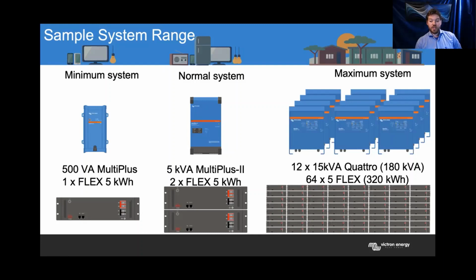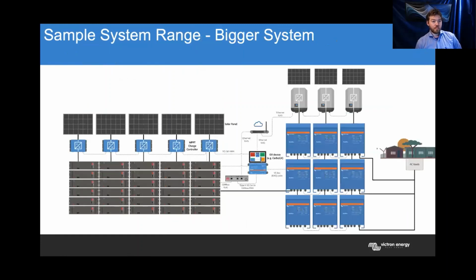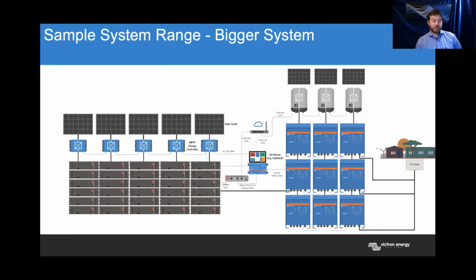Keep in mind, Paul mentioned, but stacking those batteries without a cabinet, without an external frame, is limited to 4 high. So consider that real estate and how you're going to manage all those strings, of course. It's a lot of power to balance, but nevertheless, that's the number that can be controlled by the BMU. Here's an example system diagram of something like that. In this case, those batteries would be in a cabinet to be stacked 6 high like that. These batteries are perfectly capable of supporting our 3-phase range, or batteries connected, inverter chargers connected in parallel as well.